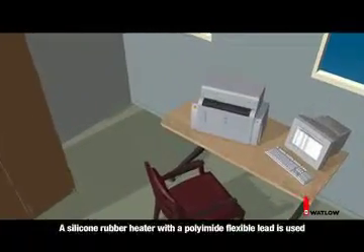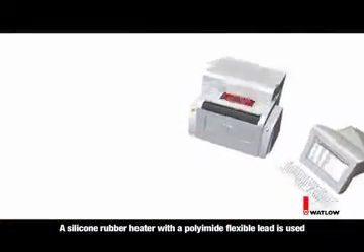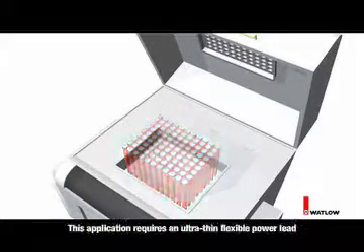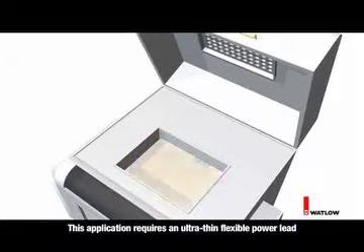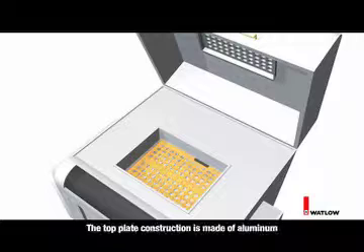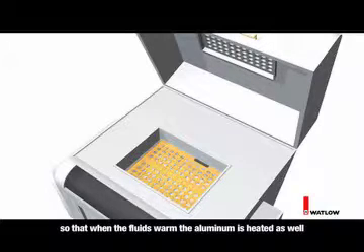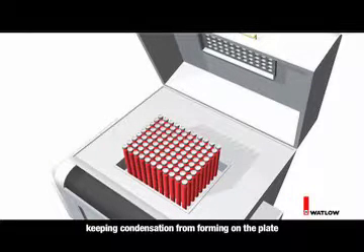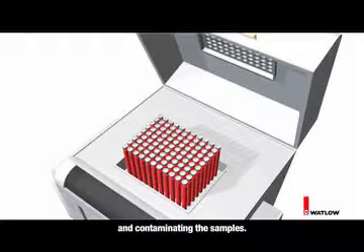A silicone rubber heater with a polyimide flexible lead is used in clinical laboratory diagnostic equipment. This application requires an ultra-thin flexible power lead that also incorporates the sensor leads with the power leads. The top plate construction is made of aluminum so that when the fluids warm, the aluminum is heated as well, keeping condensation from forming on the plate and contaminating the samples.